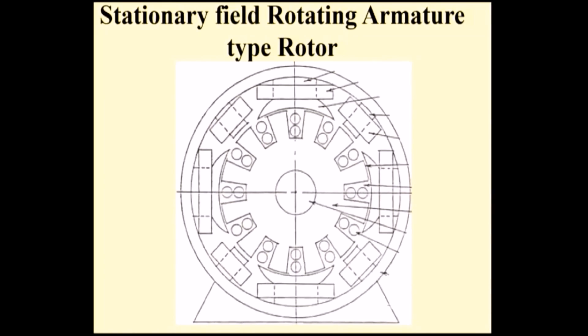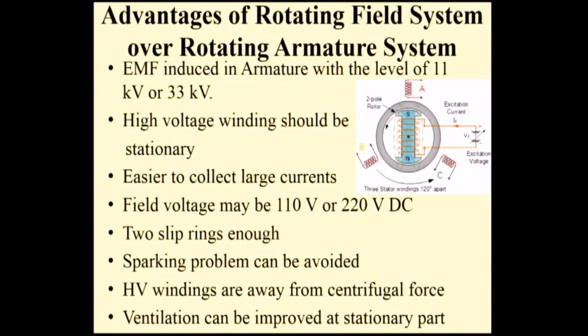There is an obvious question: which one is best? The rotating field stationary armature is the best. Why? Because most alternators operate at 11 kV or 33 kV — that is 11,000 volts or 33,000 volts. Such high voltage is induced in the armature. If that high-voltage winding is stationary, it is much better — that is why the stationary armature rotating field configuration is preferred.